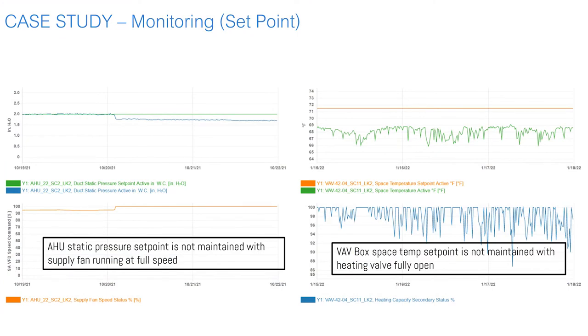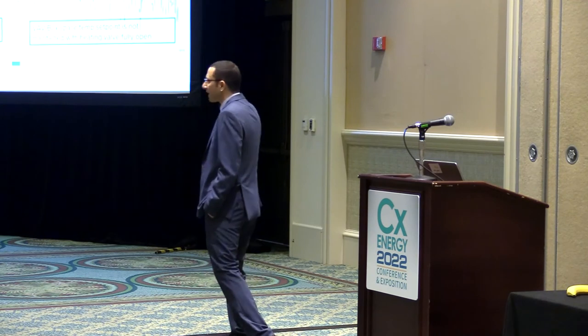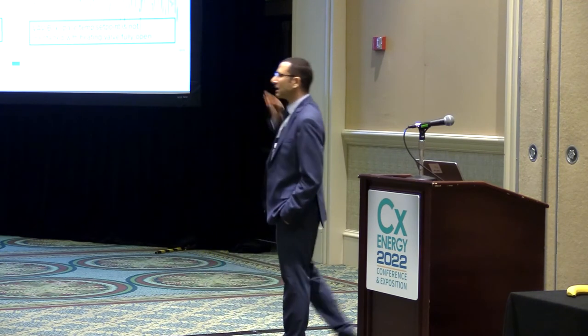Same thing here, we cannot maintain on a VAV box. Space temperature is not met while the valve is 100% open. Again, the control vendor would say, Victor, my control system is working exactly how it's supposed to. It's fine-tuned, it's trying its best to maintain, it just cannot maintain it.